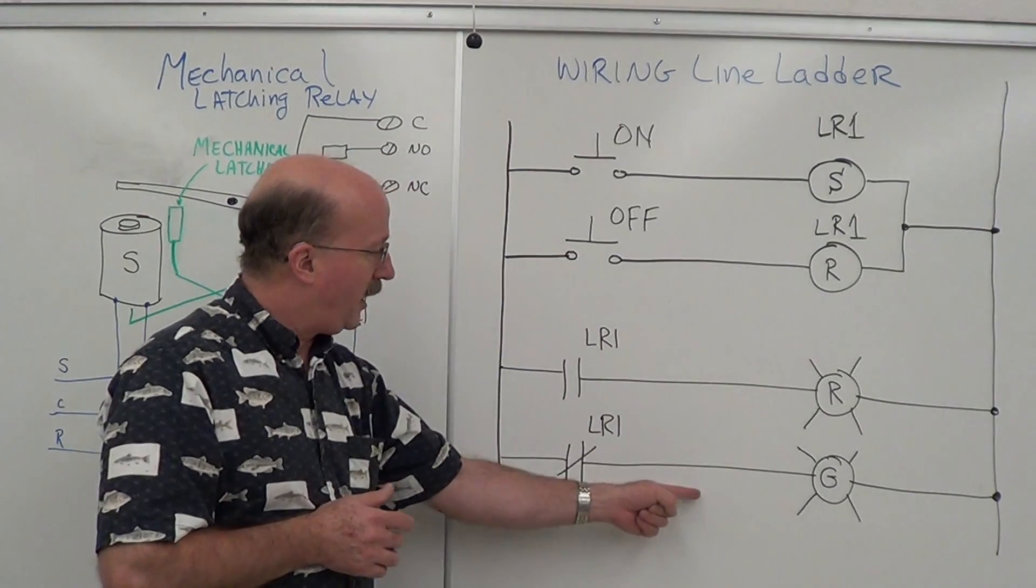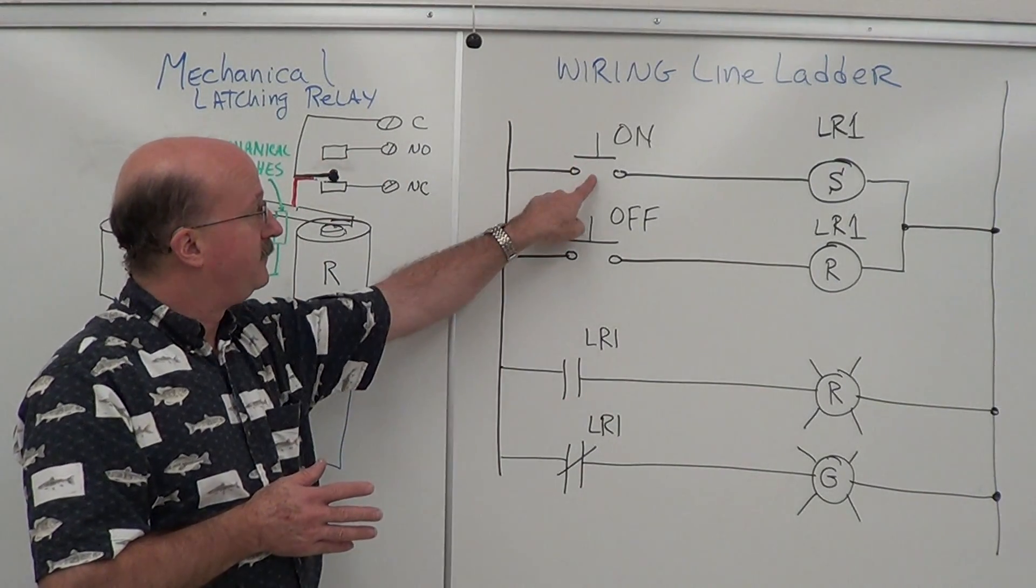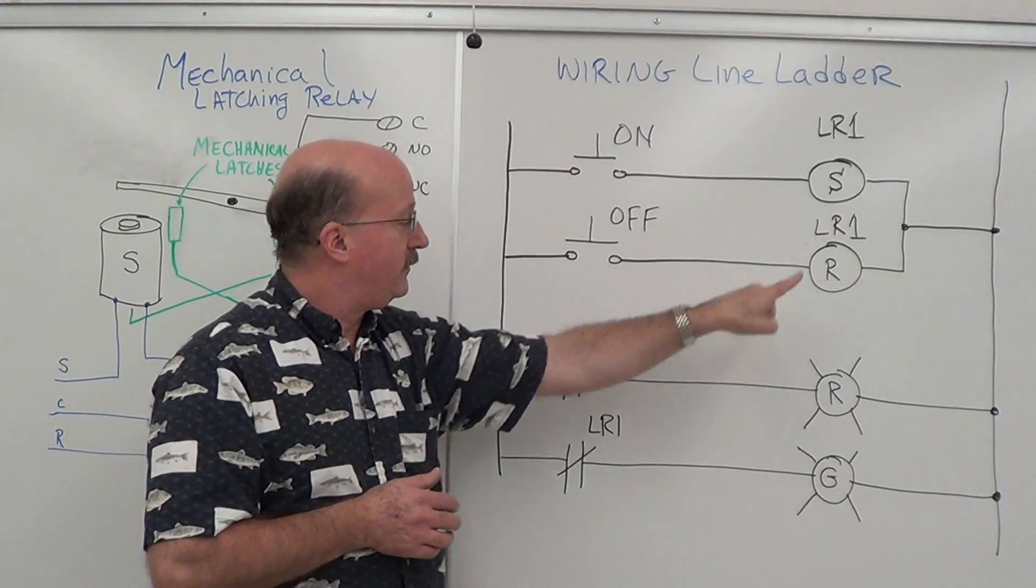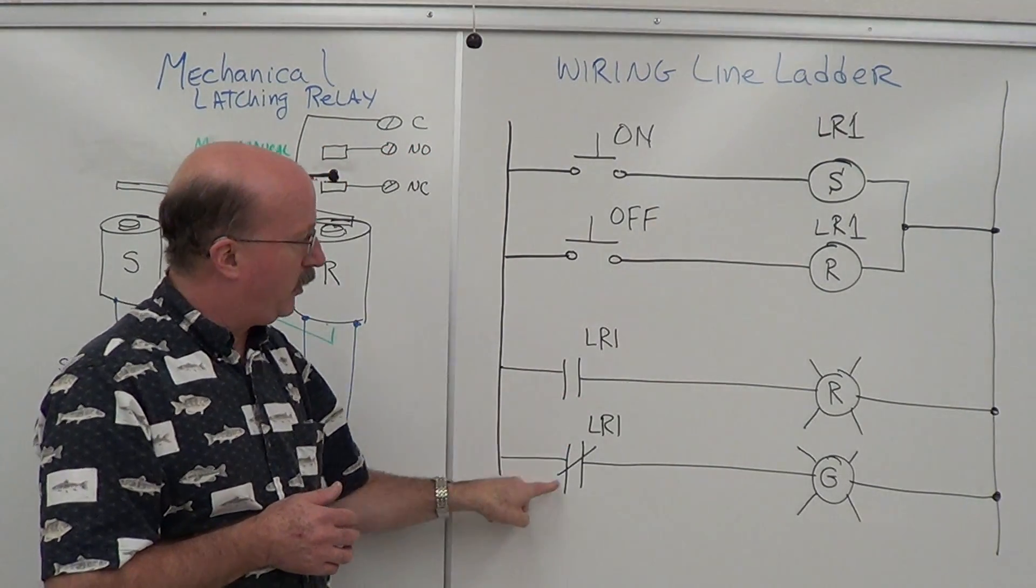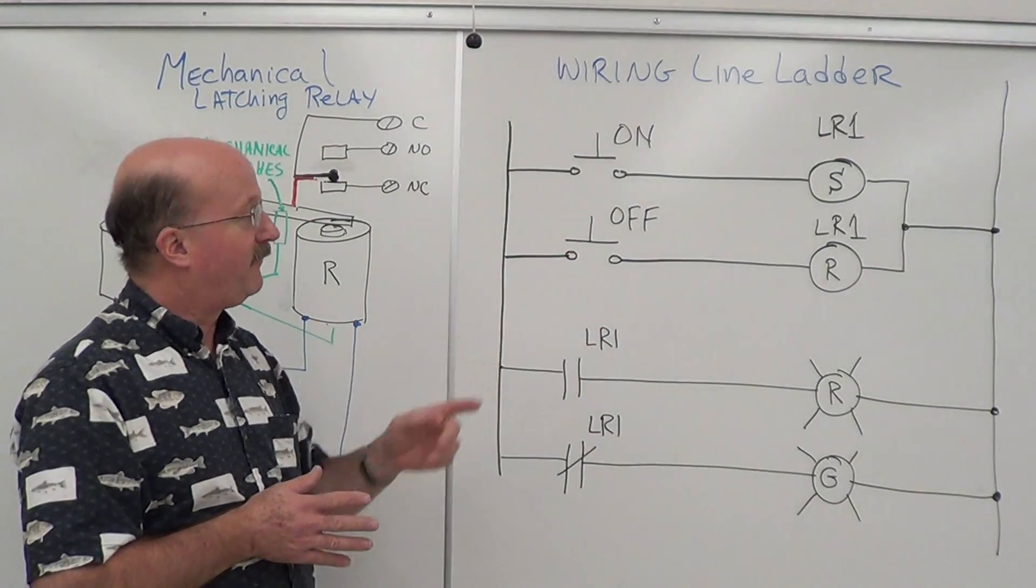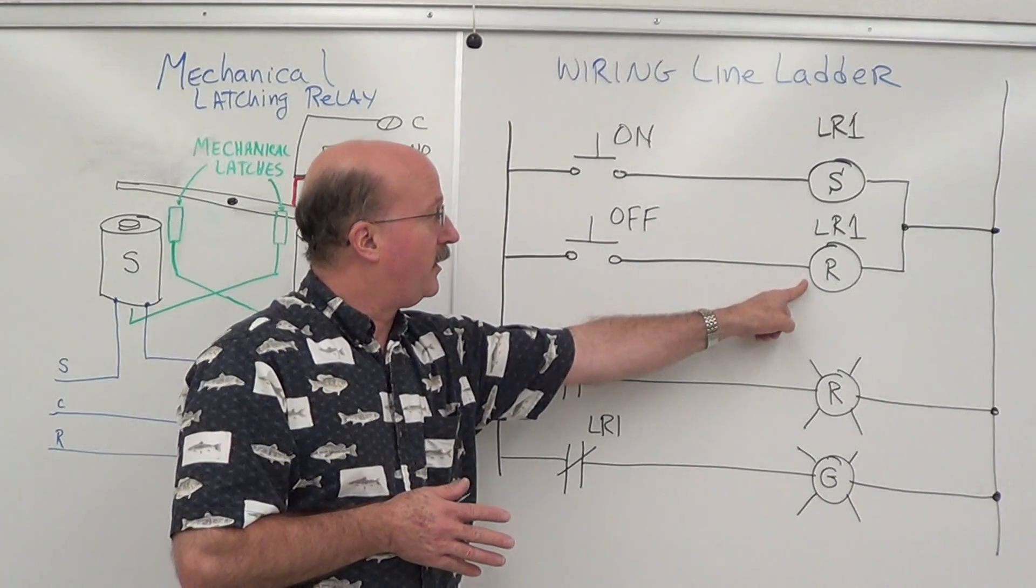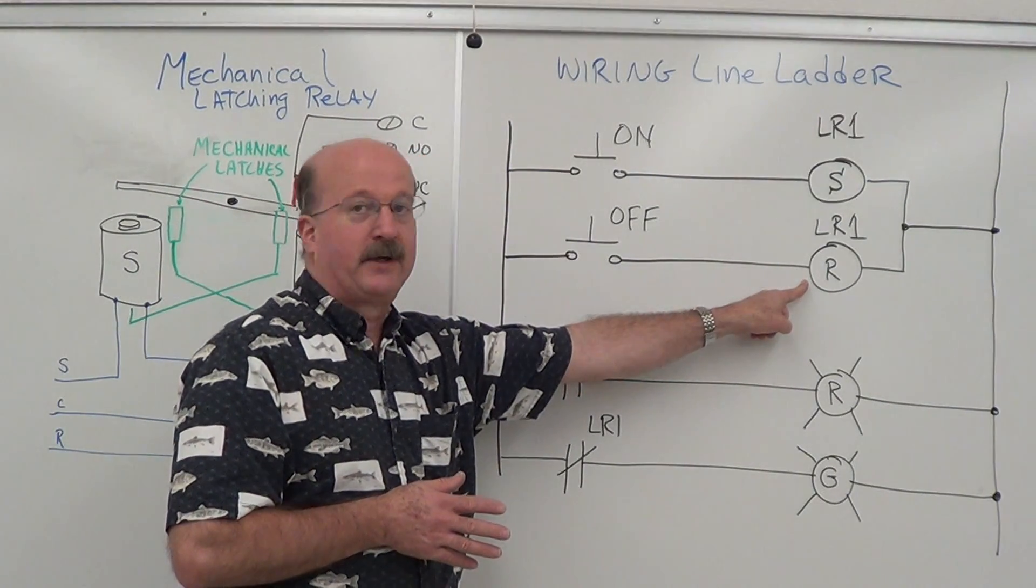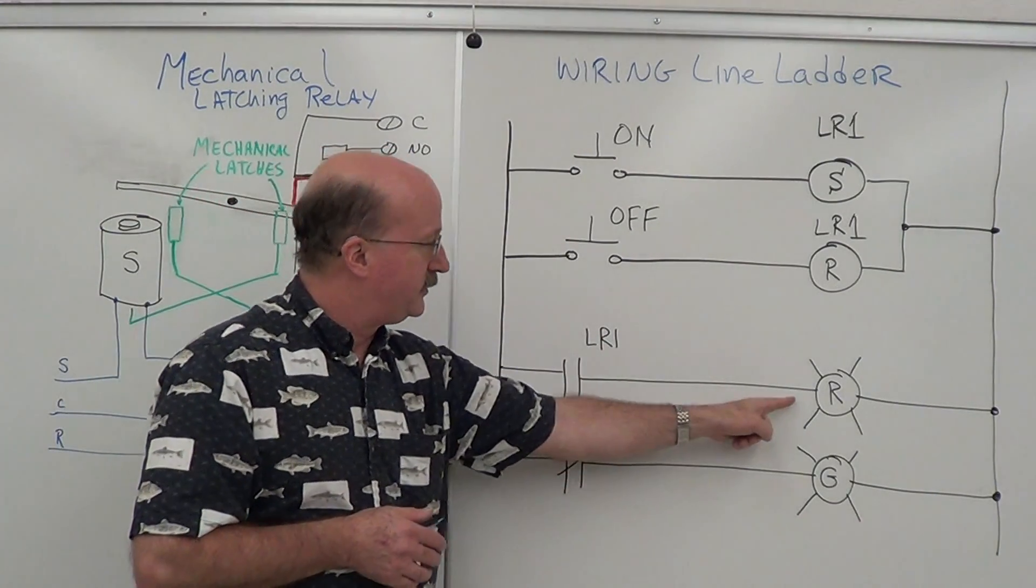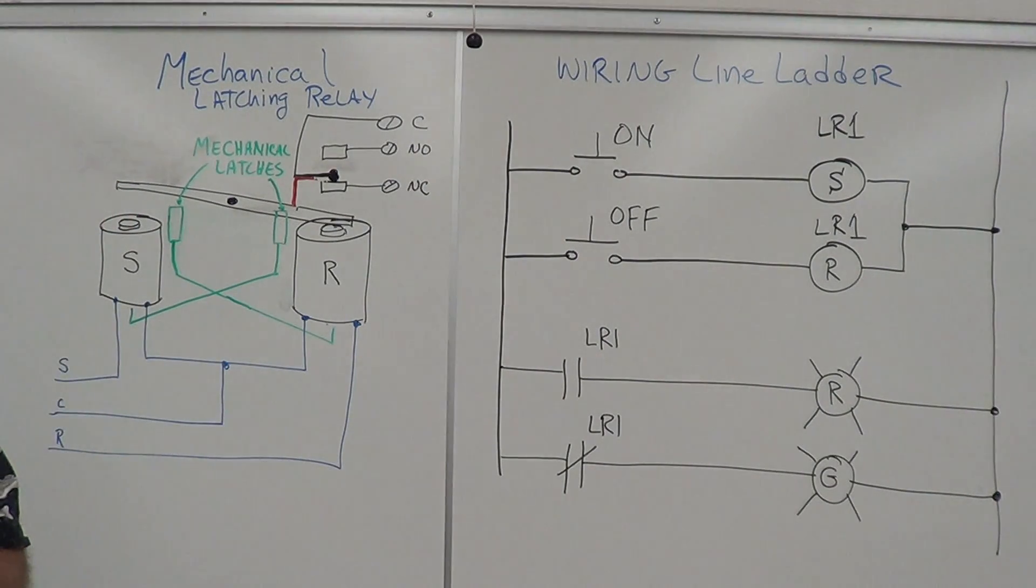So if we look at this in the off condition, red light will be off, green light will be on. I push the on button, energizes the set or the on coil. This will close, that will open. Red light on, green light off. Push the off button, energize this coil, latches release, mechanical movement moves. This opens up, that closes. Red off, green on.